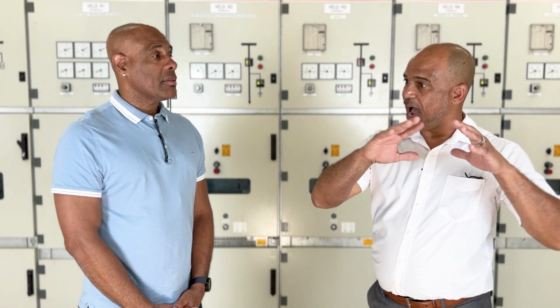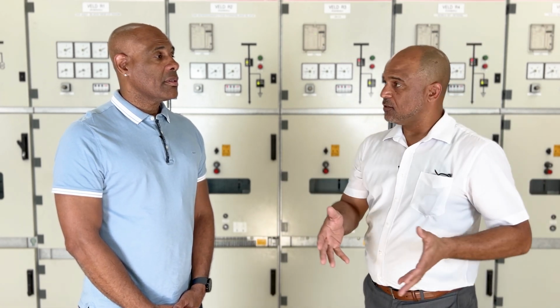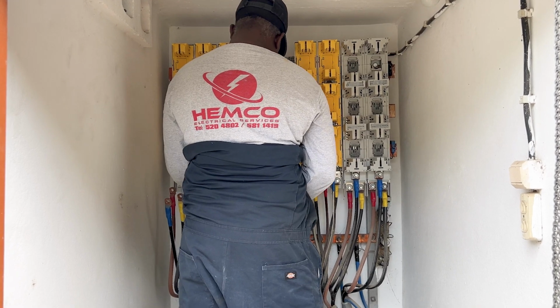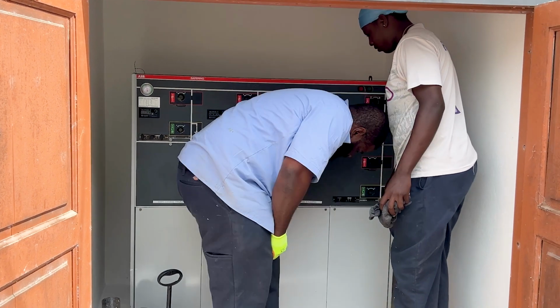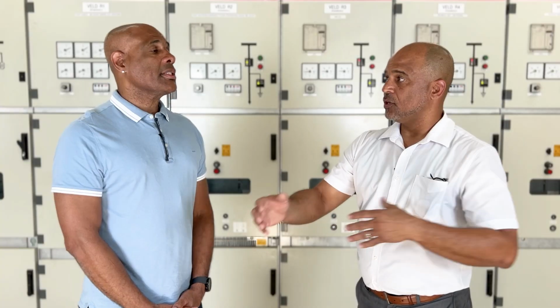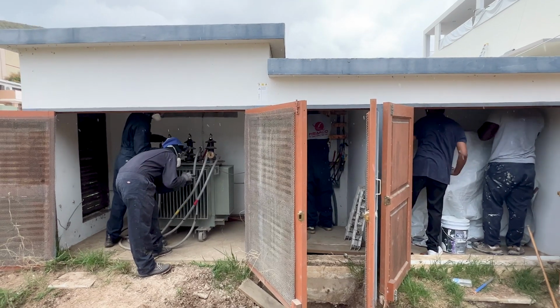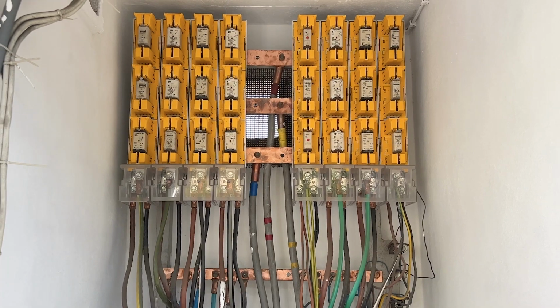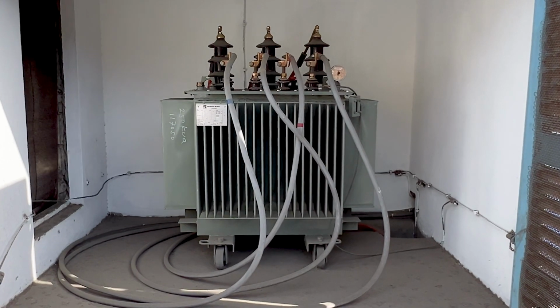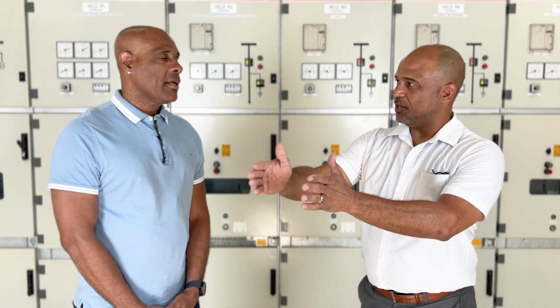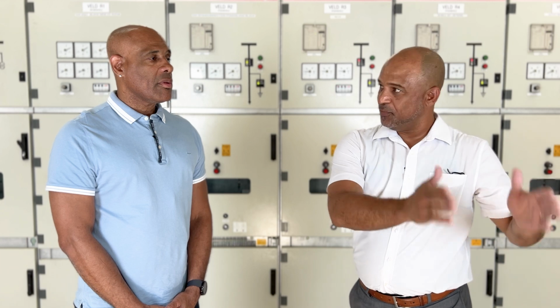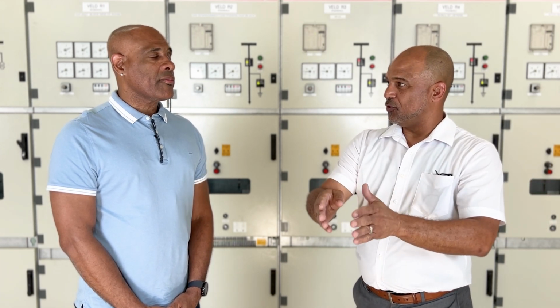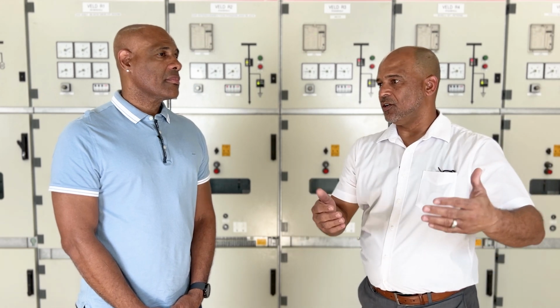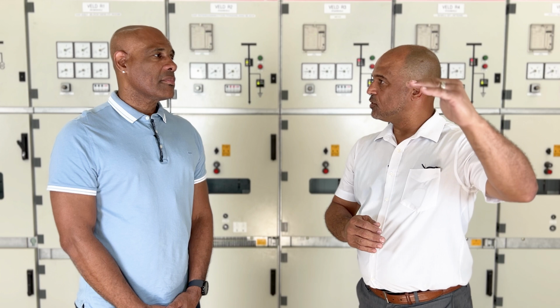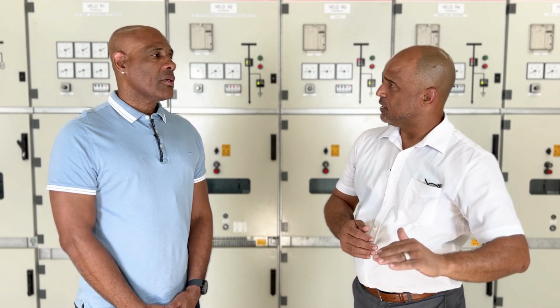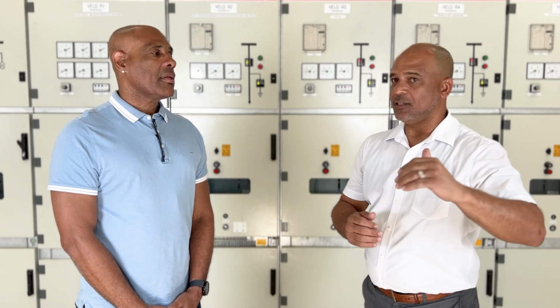And we do the high voltage switch gear as well. So we have contractors that help us out with the low voltage part and the transformer. And then we have our guys who are certified who do the cleaning of the high voltage switch gear. So there are three rooms in one transformer. You have a transformer room, there is a low voltage room, and there's a high voltage room where these cables from this substation go into. And from that switch, there is a smaller cable that goes to the transformer. And from the transformer, there are low voltage cables going to the low voltage bus bar. So from the transformer, depending, of course, on the variation of the voltage, you can go from 12,600 volts or 12,300 volts, go to 127, 220, or to 460, 480, what we also have in our grid.